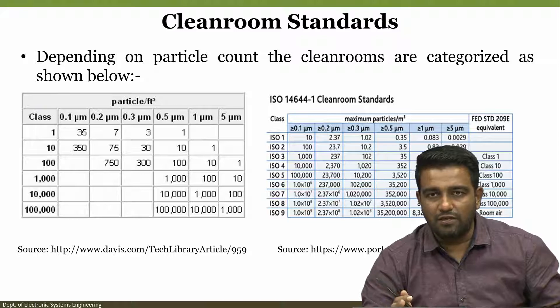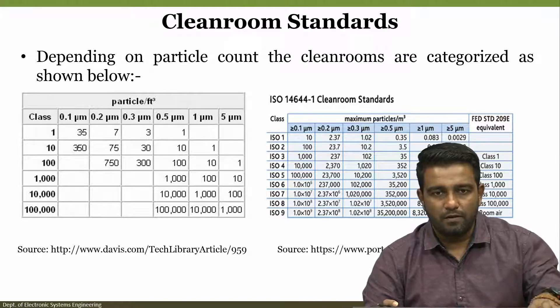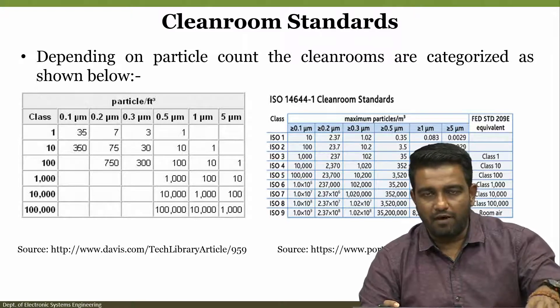Depending on the particle count, clean rooms are categorized as shown in the slide. They are categorized based on particles per cubic foot, ranging by particle sizes of 0.1, 0.2, 0.3, 0.5, 1, and 5 microns. Class 1 is cleaner than class 10, class 10 is cleaner than class 100, and class 100 is cleaner than class 1,000 to 10,000 to 100,000.